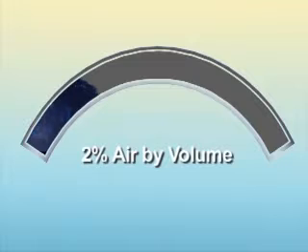Another source is the water itself. Water contains roughly two percent air by volume. During system operation, the entrained air will continuously separate out of the water and accumulate at the system high points. This two percent of air has the potential to become massive. A 1,000 foot length of pipe could contain a pocket of air 20 feet long if all the air accumulated in one location. A 1 mile length of pipe could contain a 100 foot slug. This would be true regardless of the diameter of the pipe.